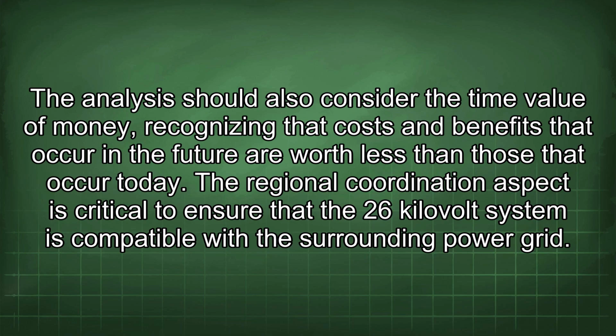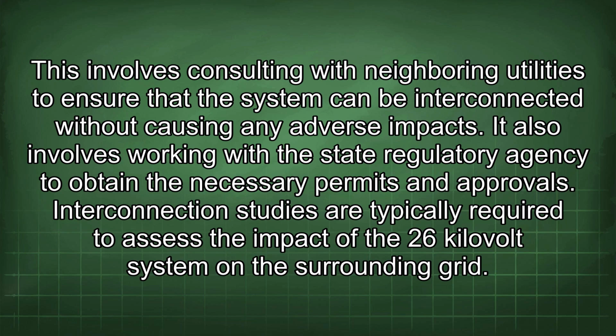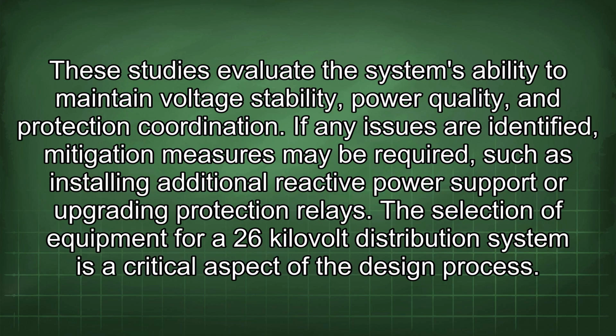The regional coordination aspect is critical to ensure that the 26 kV system is compatible with the surrounding power grid. This involves consulting with neighboring utilities to ensure that the system can be interconnected without causing any adverse impacts. It also involves working with the state regulatory agency to obtain the necessary permits and approvals. Interconnection studies are typically required to assess the impact of the 26 kV system on the surrounding grid. These studies evaluate the system's ability to maintain voltage stability, power quality, and protection coordination. If any issues are identified, mitigation measures may be required, such as installing additional reactive power support or upgrading protection relays.